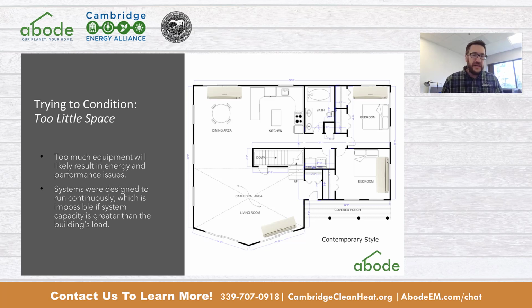And this is, I really have 4 rooms in here. I'm going to just put in 4 units. But the problem with this is, let's pretend that the load on this home is actually 2 tons. The smallest outdoor unit that can handle 4 pieces of indoor equipment is 3 tons. So what ends up happening is this equipment, because you wanted to put 4 units in, is 1/3 oversized.